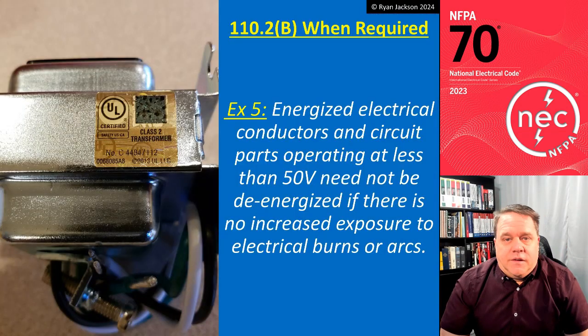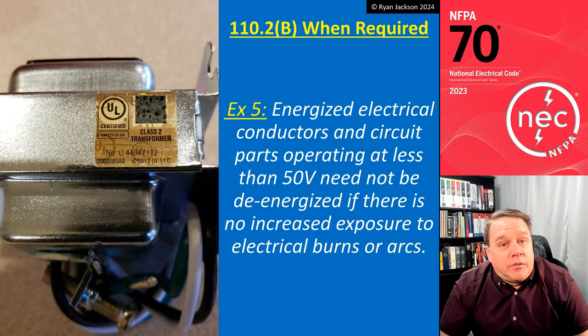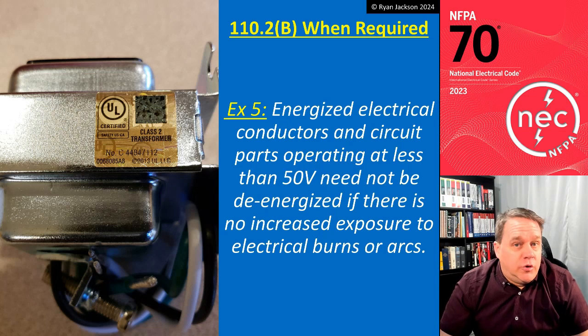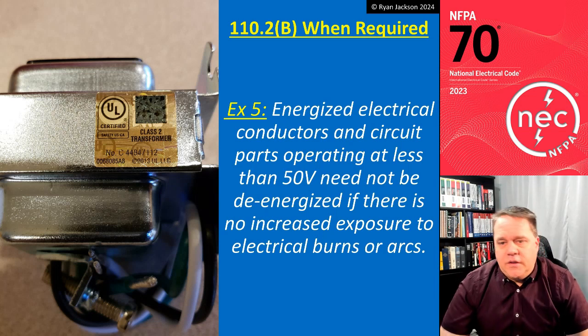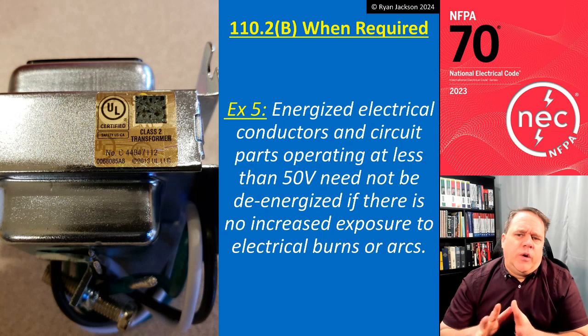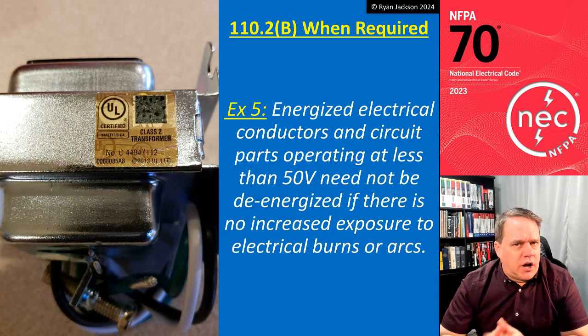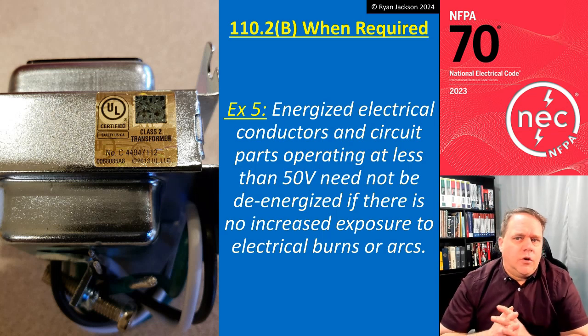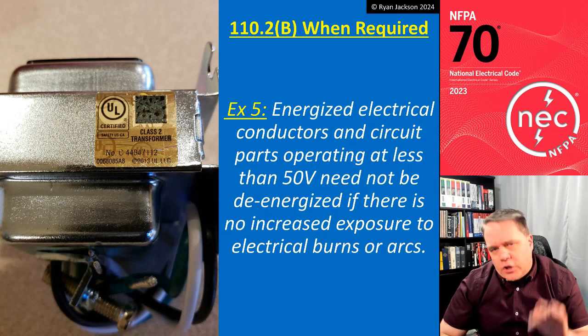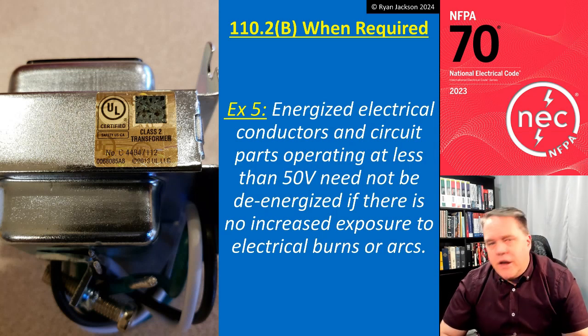Exception number 5. Energized electrical conductors and circuit parts operating at less than 50 volts need not be de-energized if there's no increased exposure to electrical burns or arcs. All right, so 50 volts is where we start getting concerned from a shock perspective. If it's lower than 50 volts, you can't get enough current to create a fatal condition.